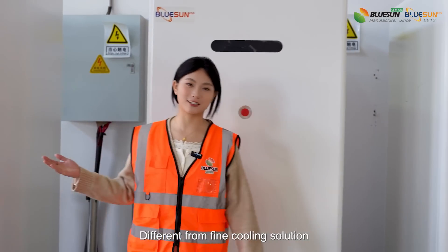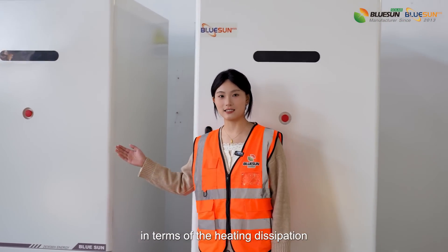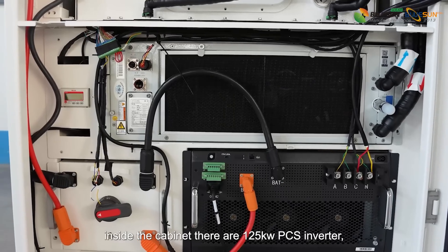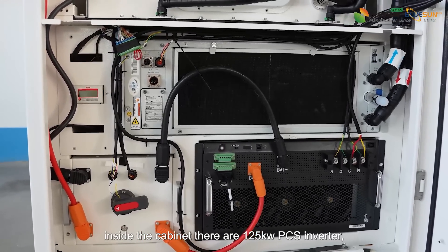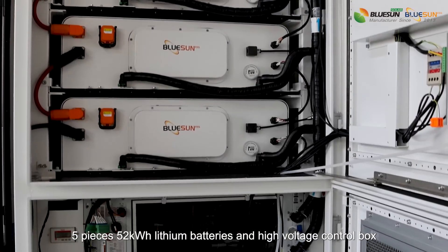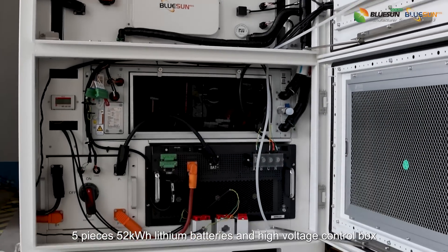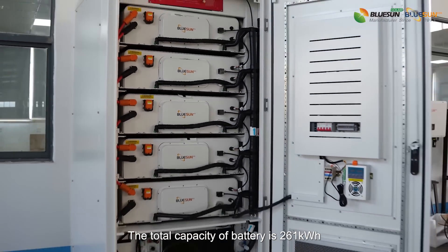Different from a fan cooling solution, this system has better performance in terms of heat dissipation. As you can see, inside the cabinet there are a 125kW PCS inverter, 5 pieces 52kWh lithium batteries, and a high voltage control box. The total capacity of the battery is 261kWh.